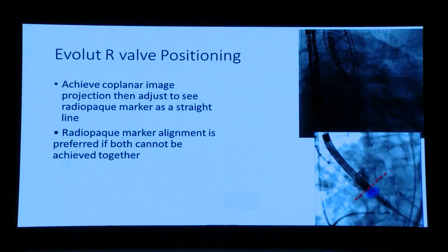Even when we move the valve from the groin up, we have to monitor with fluoroscopy, monitor the LV wire. We can move gradually, and when we move the LAO, we cross the arch and then enter the LV. The target implant depth is 3 to 5 millimeters. As you can see in this picture, the inflow edge, the lowest portion of the frame, is node 0. Node 1 is the first marker band. The distance between node 0 and node 1 is 6 millimeters. So our target implant depth is 3 to 5 millimeters, in a typical tricuspid valve.